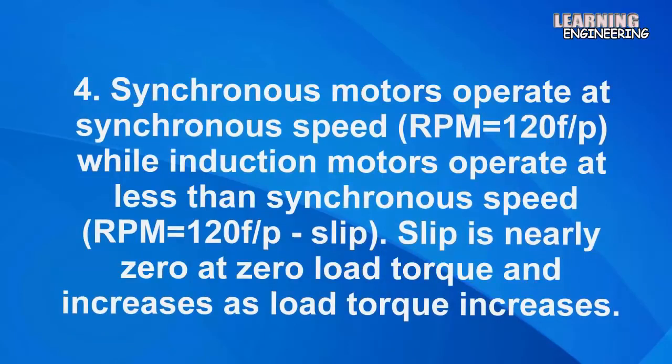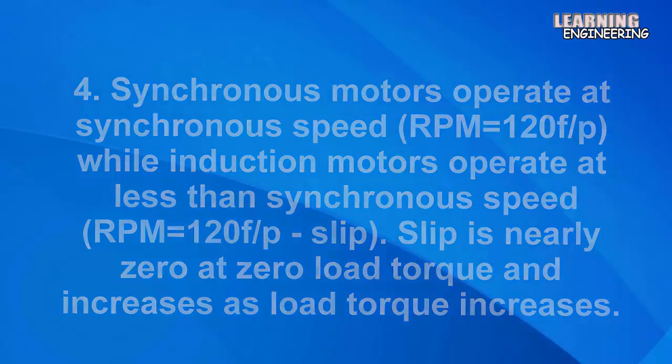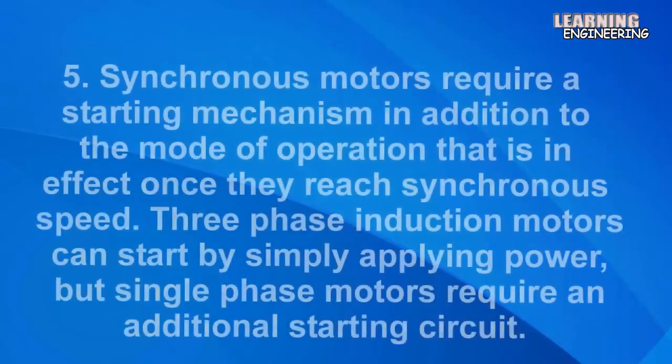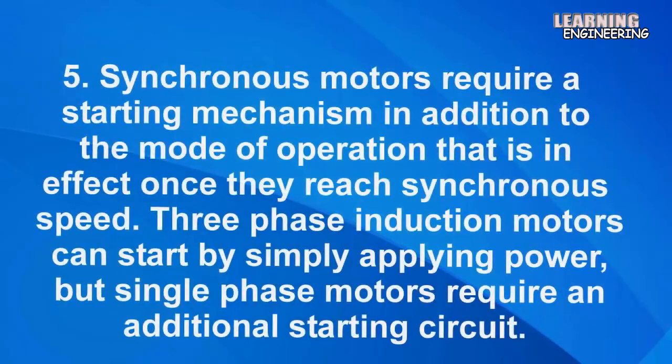Four, synchronous motors operate at synchronous speed (rpm = 120f/p), while induction motors operate at less than synchronous speed (rpm = 120f/p - slip). Slip is nearly zero at zero load torque and increases as load torque increases.